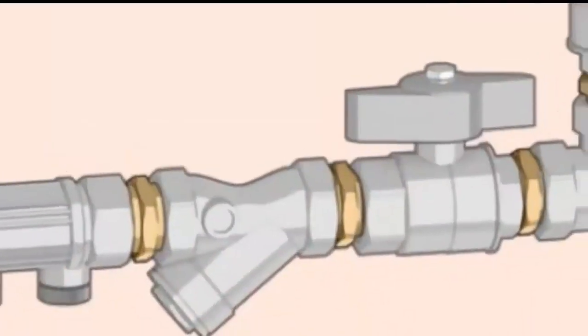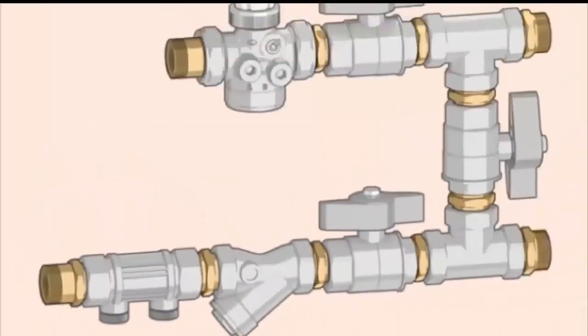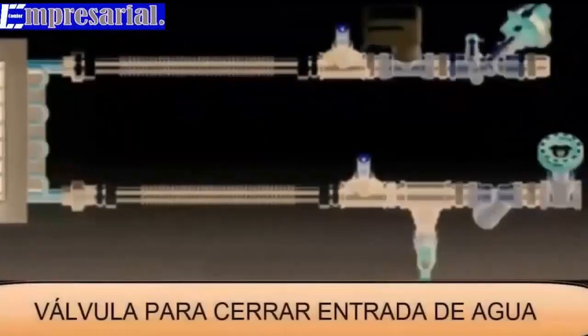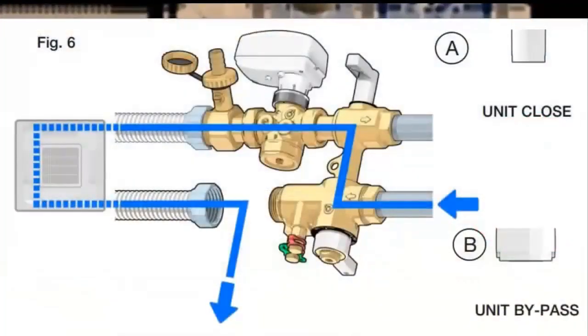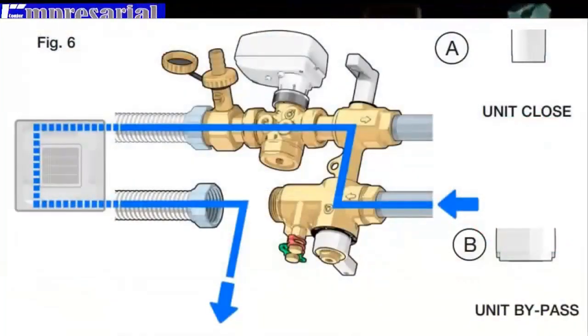Water filter at the entrance: in order to prevent impurities in the water from entering the system. Valve DRV: this double function valve allows us to regulate the flow of water as independently as possible of the pressure. Gate valves at the inlet and outlet: in case of any maintenance, these valves seek to close the total flow of water to the exchanger.